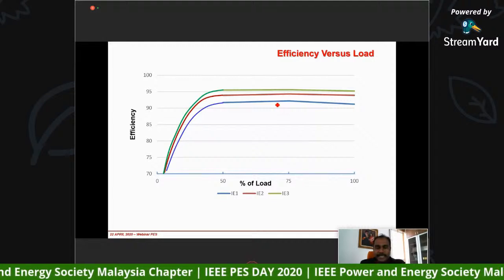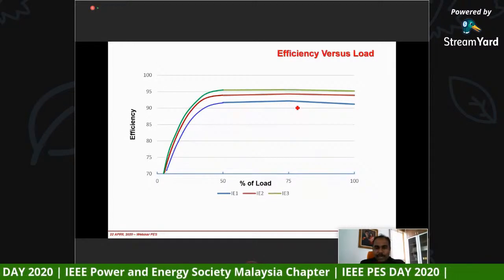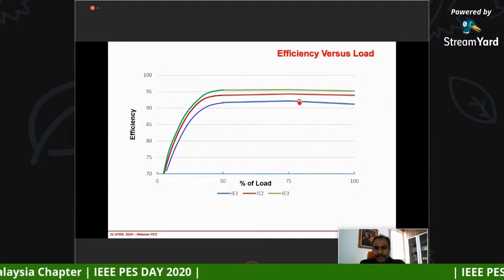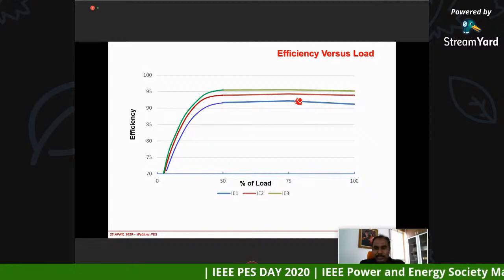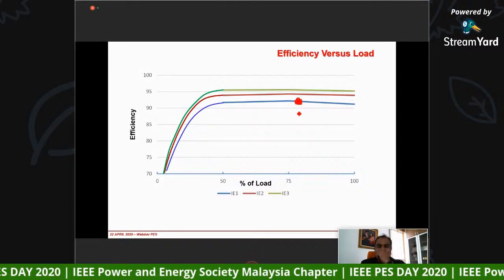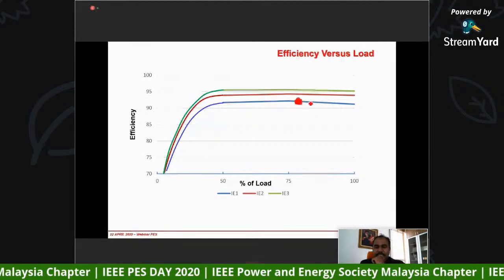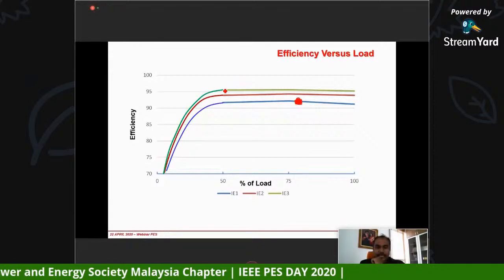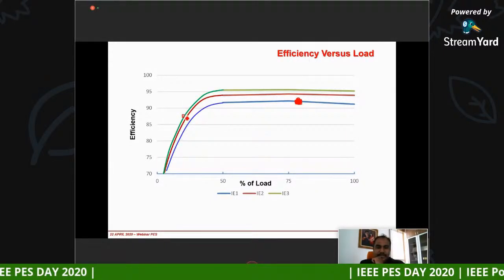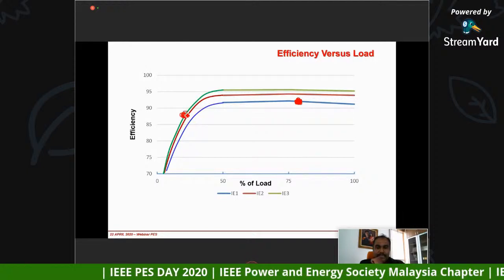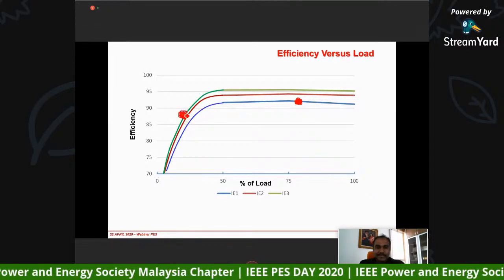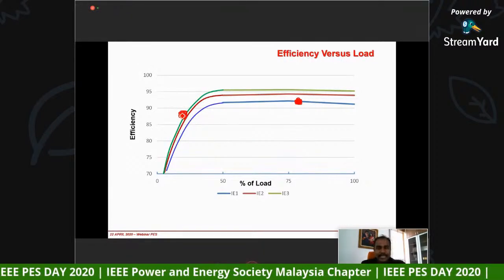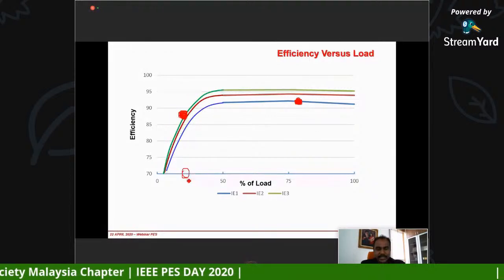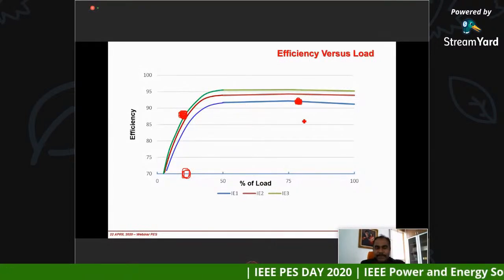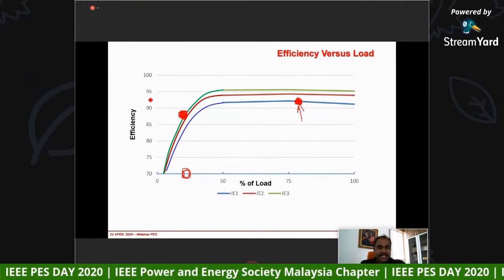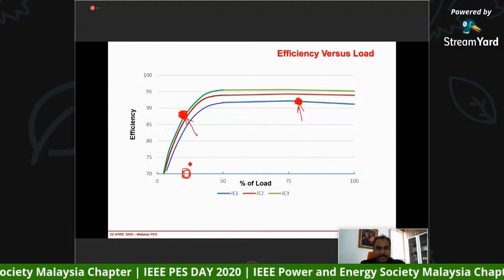Let's say I have an IE1 motor, which is operating at about 80%. That means here, this is the IE1 motor. Now I have another system which is IE3, this is IE3, the green one, but it is operating at 40%. Let's say that particular system, the load is so light, or in other words, the motor was actually oversized. That means it's operating at a light load. You can see here, even though I'm using IE1, the efficiency is higher compared to the IE3 motor because the load is actually low.